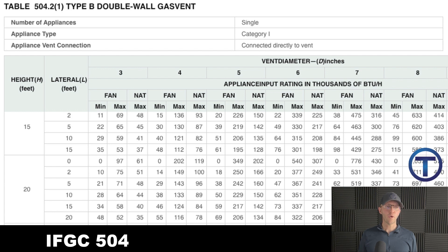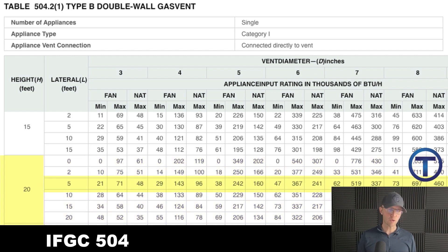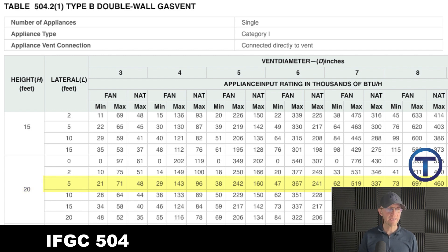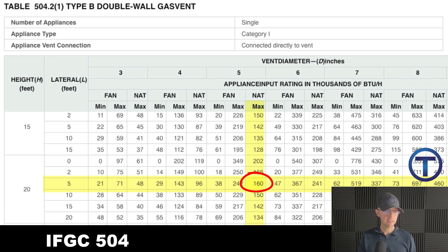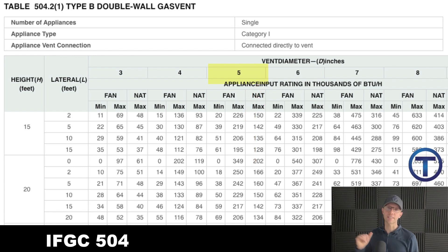Let's figure this out. We've got Table 504.2.1. If I have 20 feet of height, I come down and there are rows that fit within 20 feet. But then I have my lateral length, which was five, so I go to the row that's five. From there I come over with my 140. It's got to be natural draft. You'll notice one column might fit 140 — like 149 there — but that's a fan max and we're not using fan. So I come across until I find 140 that fits in the natural column, which gives me 160,000 BTUs with natural at that height and lateral. I come up to the top and find a five-inch vent pipe. That's the correct answer.